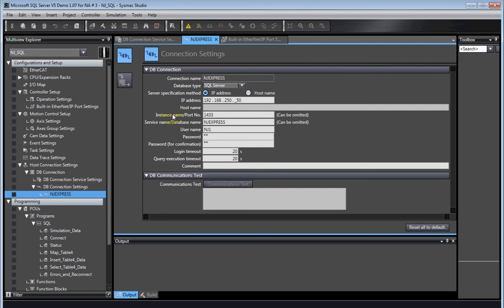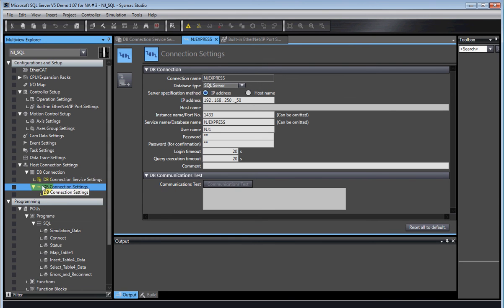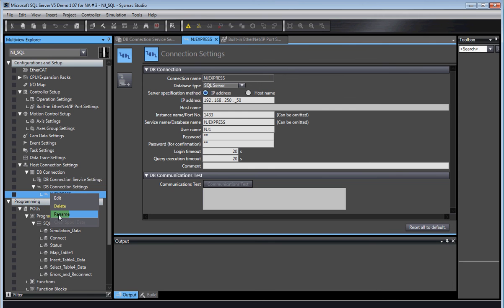Then you go to this screen, you add a connection on the NJ1 that would be one connection, on the NJ5 it can be up to three. Then you go here and you'll rename it. The name is important because you'll use it in your ladder program and it's nice if you know what it's referring to.